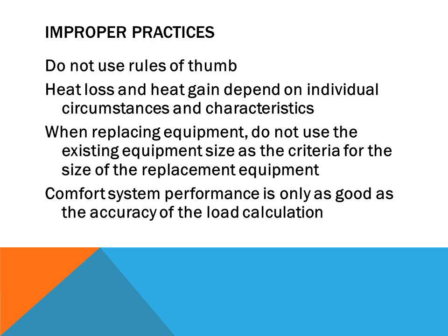So when replacing equipment, do not use the existing equipment sizes, because the newer equipment is probably more efficient, and because it's more efficient, there are fewer losses, so it could be sized slightly smaller. But then again, we still should do a heat load calculation because of the efficiencies of the equipment. If we just look at the structure without considering that, maybe the equipment was oversized in the beginning, but we should still go through and do a calculation.